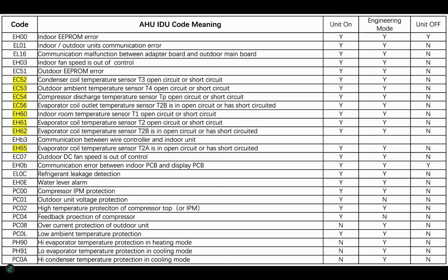The other thing to look out for is that the 5-volt DC bus is fed by the 12-volt DC bus. So you could have a 12-volt DC bus problem that shows up as this sensor error. Your 12-volt DC bus is your EEVs, the stepper motors for the EEVs. I'm trying to think what else is in that 12-volt bus. So the 12-volt bus feeds the 5-volt bus, and a problem with the 12-volt bus may show up as a 5-volt bus problem. If you're doing that, also check your EEV stepper motors.